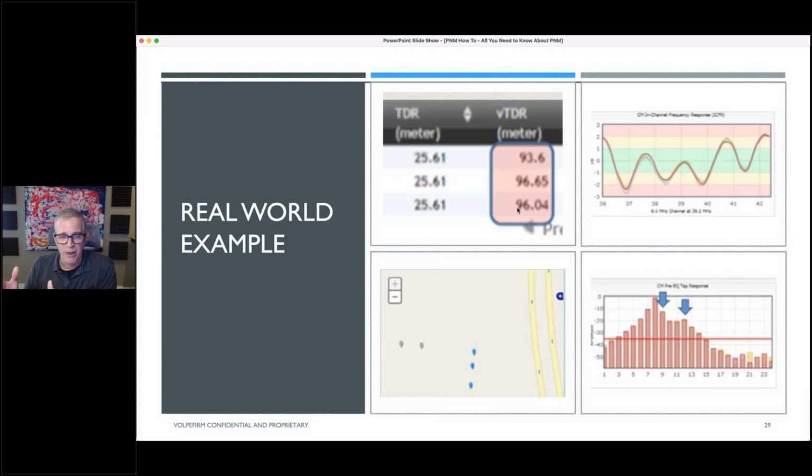Again, remember I said there are some inherent inaccuracies because we can't pinpoint this to within one foot of accuracy. So don't believe people when they say, oh, we'll nail that echo cavity down to within one foot. We can't violate the laws of physics when we only have 24 digital taps. And here's our standing wave. Remember I said the more sinusoidal waves or echoes we have, basically the more points we have on our standing wave, the further out in the outside plant it is.